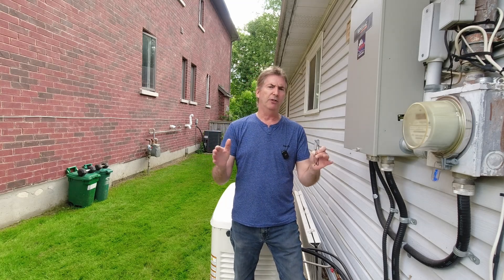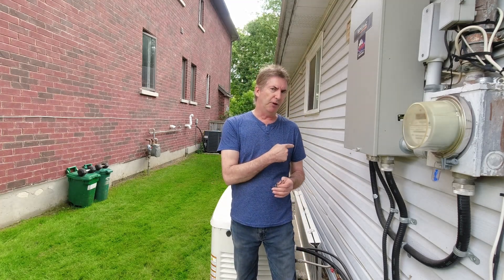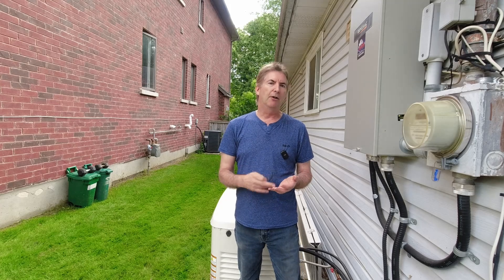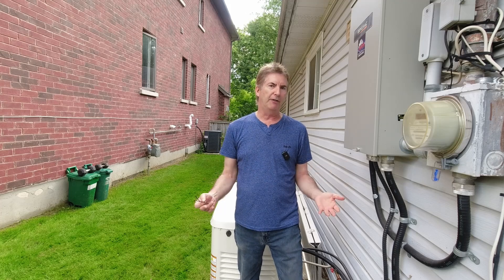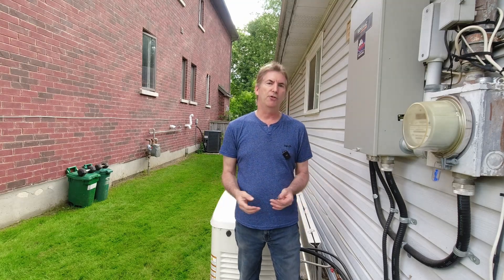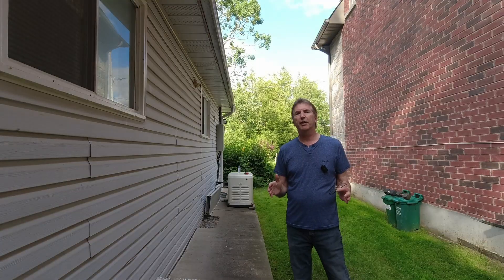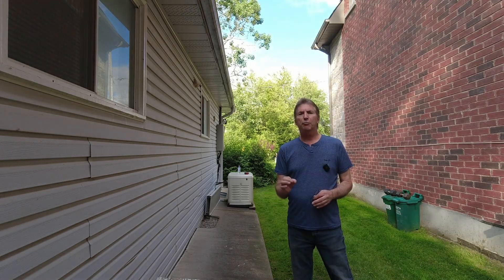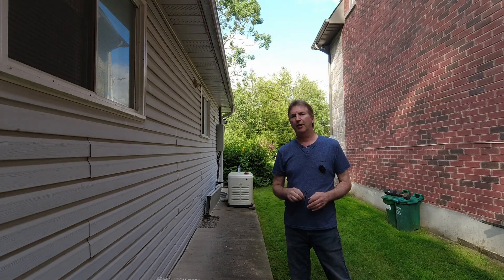I just wanted to cover what to do in that situation. Now, in this case, because his window was open, he did have CO in the house and his alarm was good — but he didn't call the fire department. He called an independent contractor who services the equipment, and by the time he got there the windows had been opened and there was nothing left in the house. So was it a defective CO detector? You don't know for sure, but obviously with the testing, it was exhaust fumes going in through that window. That's my video on the 11-kilowatt Generac generator and carbon monoxide — the potential dangers of improper installation. If you liked the video, I appreciate a thumbs up, subscribe, and hit the bell. Thanks for watching.